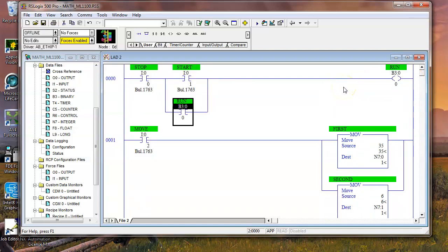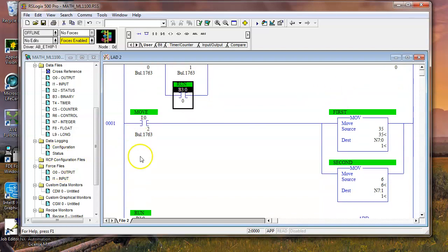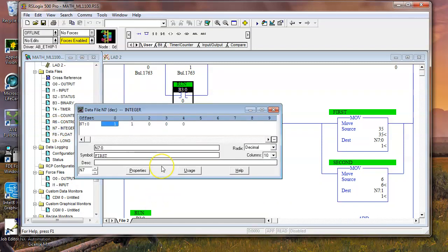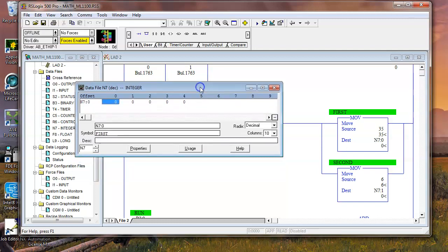So what we would do, if we're going to turn the whole thing off, and we got a little problem with this, in that when we come up here and originally load the program, we're using N7, or it doesn't make any difference which one we're using. When we originally load up the software or the application the first time, we end up with zeros in our registers. So as soon as the program goes to run, it faults, and it's a major fault. And what's the problem?